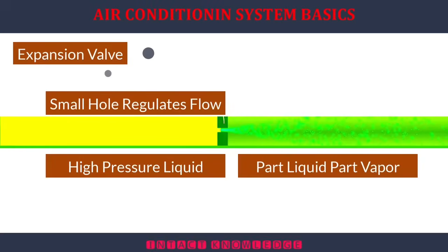The expansion valve regulates the refrigerant by only allowing it to pass through a small hole. This creates a large pressure difference across the valve. One side is the high-pressure liquid, the other side is almost empty. The small hole causes it to almost spray into the evaporator as a part liquid, part vapor mixture. The refrigerant will expand to try and fill the empty space on the other side, and this will cause it to drop in pressure as well as temperature.